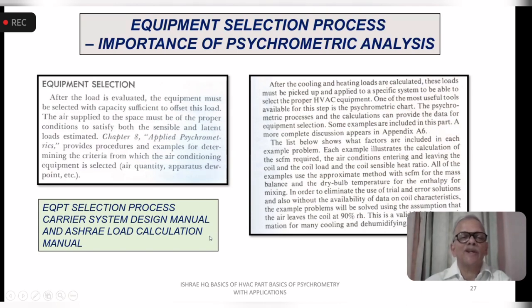This is from the ASHRAE load calculation. Similar statement, but the method is slightly different. After the cooling and heating loads are calculated, these loads must be picked up and applied to a specific system to be able to select proper equipment. One of the most useful tools available for this step is the psychrometric chart. The psychrometric processes, which we have tried to understand, and the calculations can provide the data for the equipment selection. So this will tell you what capacity equipment is required.